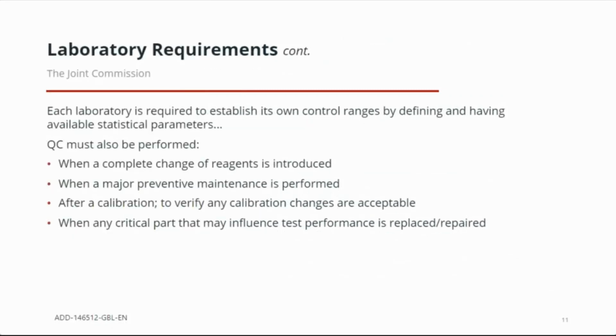The Joint Commission is another accrediting agency in the United States. They state that each laboratory is required to establish its own control ranges by defining and having available statistical parameters. QC must also be performed when a complete change of reagents is introduced, when major PM is performed, after a calibration, and after any critical part that could influence test performance is replaced or repaired.